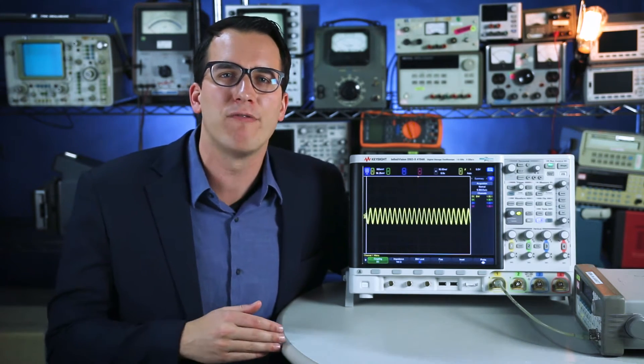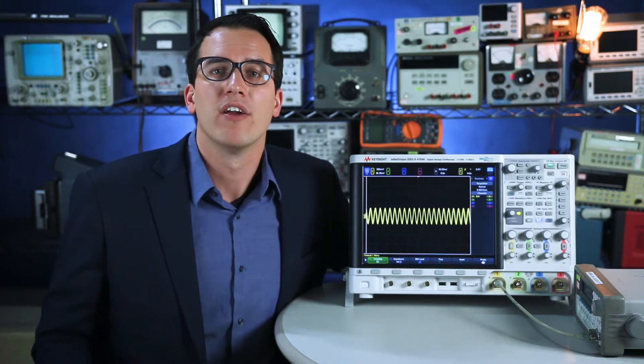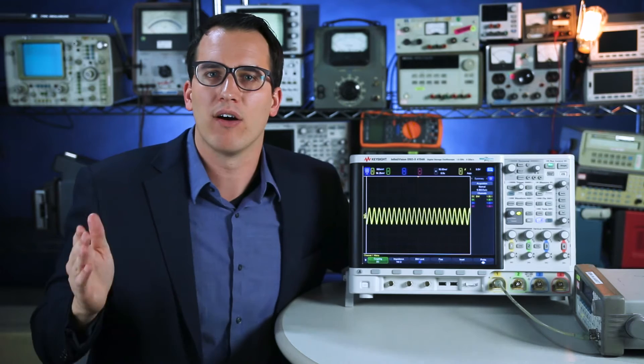Sample rate is the spec for digital scopes and it tells you how fast, how many points per second, your oscilloscope is actually acquiring data. So the signal is routed through the analog front end, which is where the bandwidth comes from. And then we have the digitizer sampling that analog waveform.